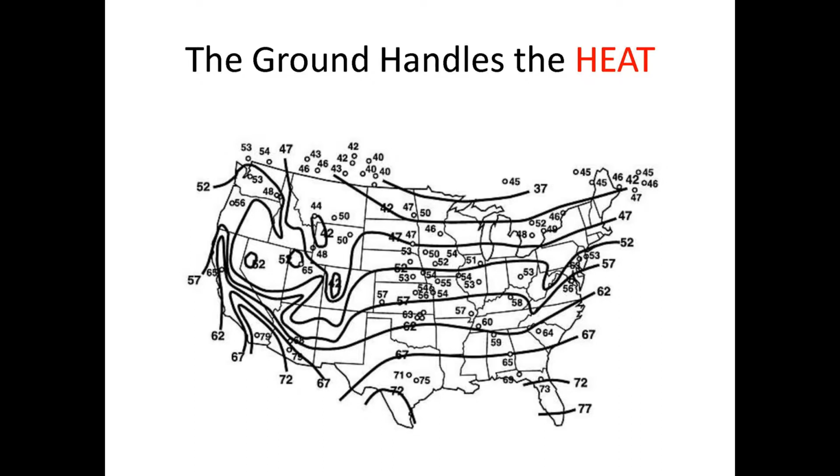So your hot water that's coming from the air conditioning going down into the geothermal wells can be over 100 degrees, maybe 110. When it goes into 67 degree ground, that's a big temperature difference. It gets rid of a lot of heat, and when the water comes back, so that's basically how that part of it works.